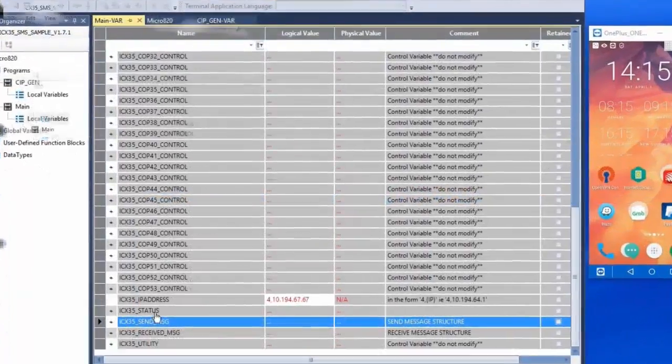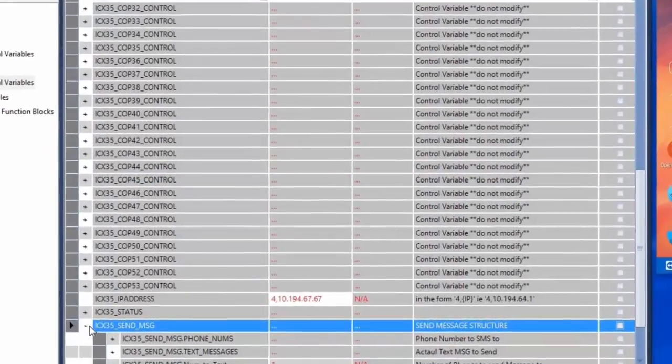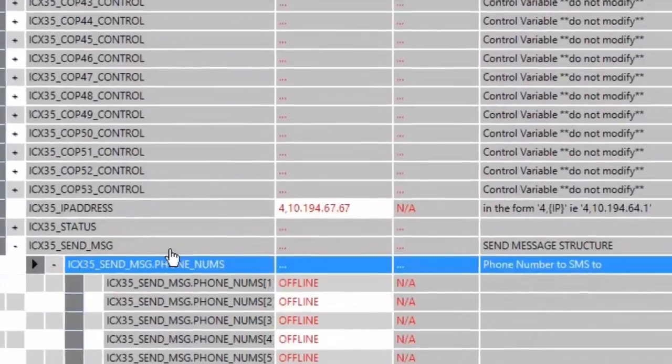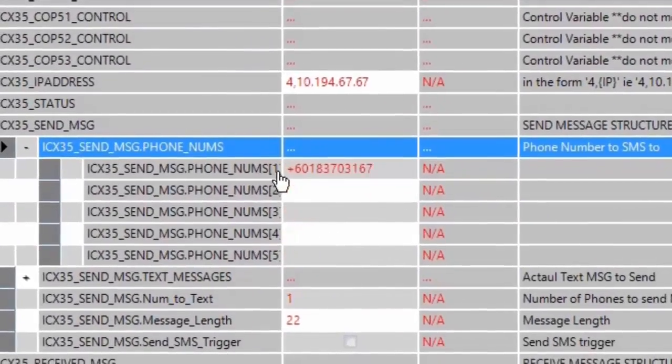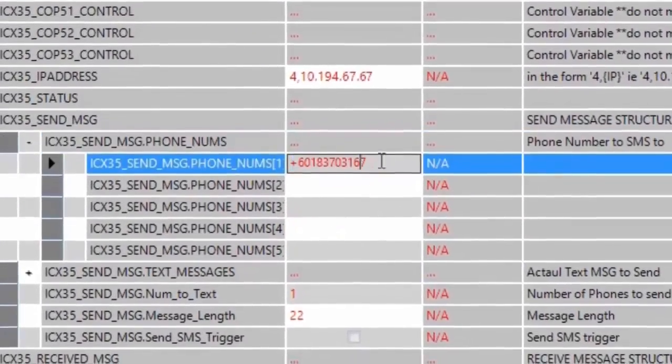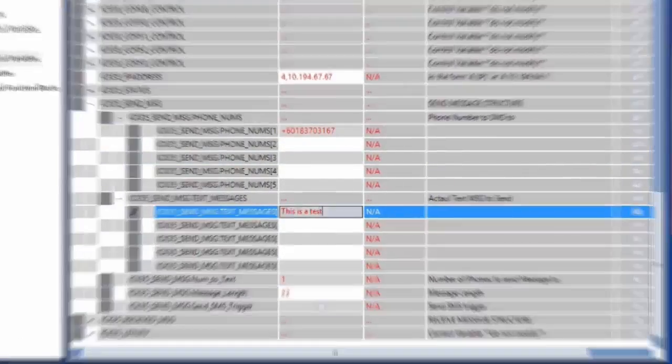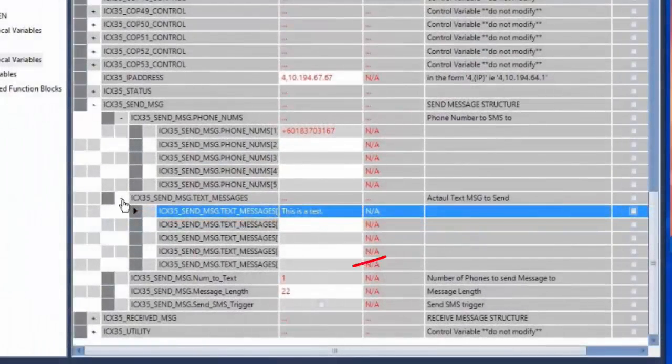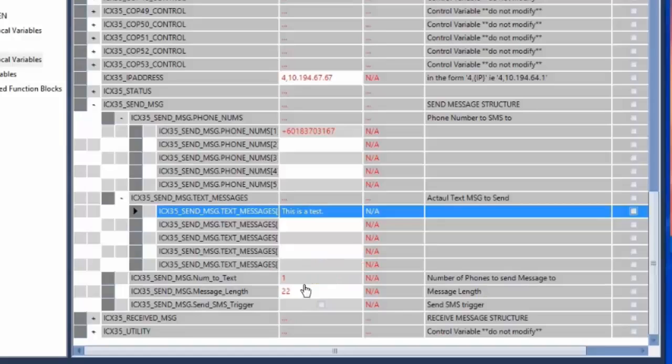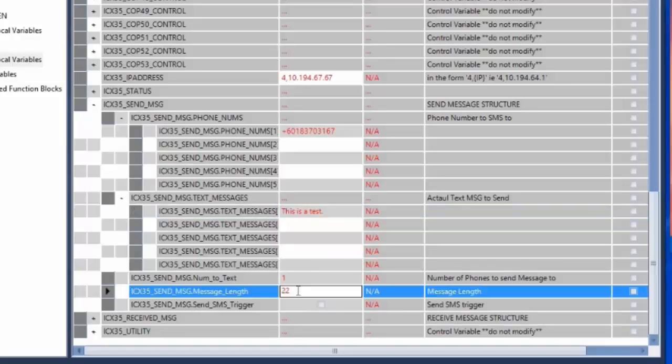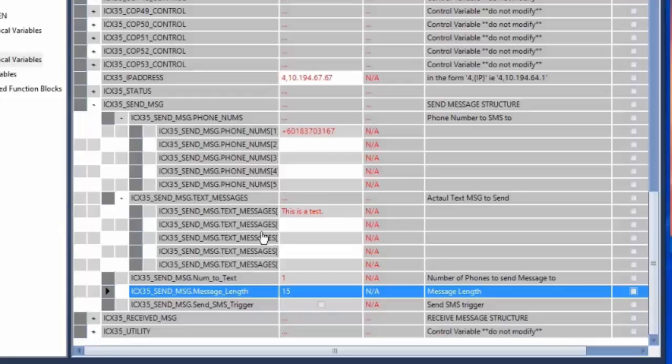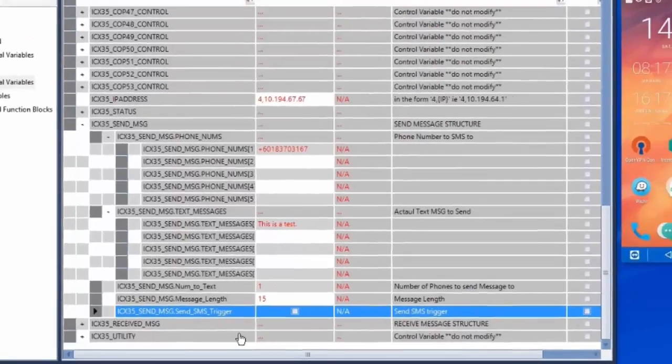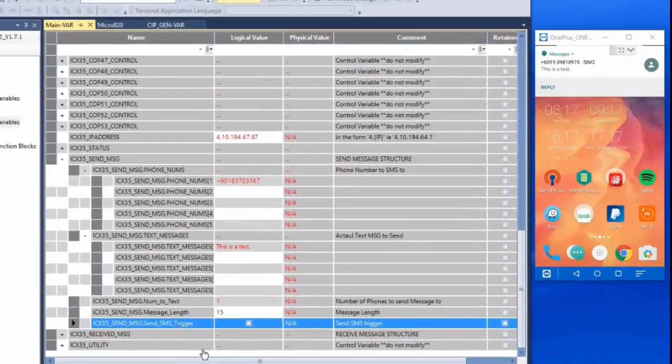So let's send a message. We'll expand the send message tag and we'll first need to enter the phone number that we want to send the message to. Next, enter the text message that you want to send out. Then we'll enter the number of phones that you want to send the message to. For this version of the sample project, you can send the same message to up to three phones simultaneously. And finally, the message character length including spaces and punctuation. Once all that is entered, the message will be sent after triggering a high signal on the send SMS trigger boolean tag. So I'll do that now. Once the message goes out and is received by the recipient, they can immediately reply to the message.